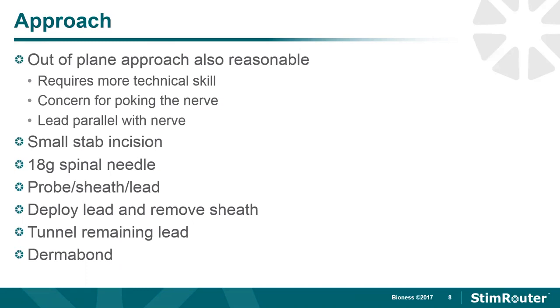But the most important reason I do that is my next step now is to remove the introducer stylet. I'll check one more time with ultrasound to make sure that white part of the sheath is still on top of the nerve. It hasn't pulled back. And then I just put the lead inside the sheath and pull the sheath out. I don't actually do stimulation at this step. I found that placing the lead visually with ultrasound when the sheath is in the correct location and simply pulling out the sheath gives me a much higher chance of first pass success when I test on the lead for that first time. And also with a pretty reasonable ultrasound machine, you can actually see where the lead is inside the sheath. It shows up very, very bright and white, so you can place it exactly on top or under the nerve. And then just pull the lead back.